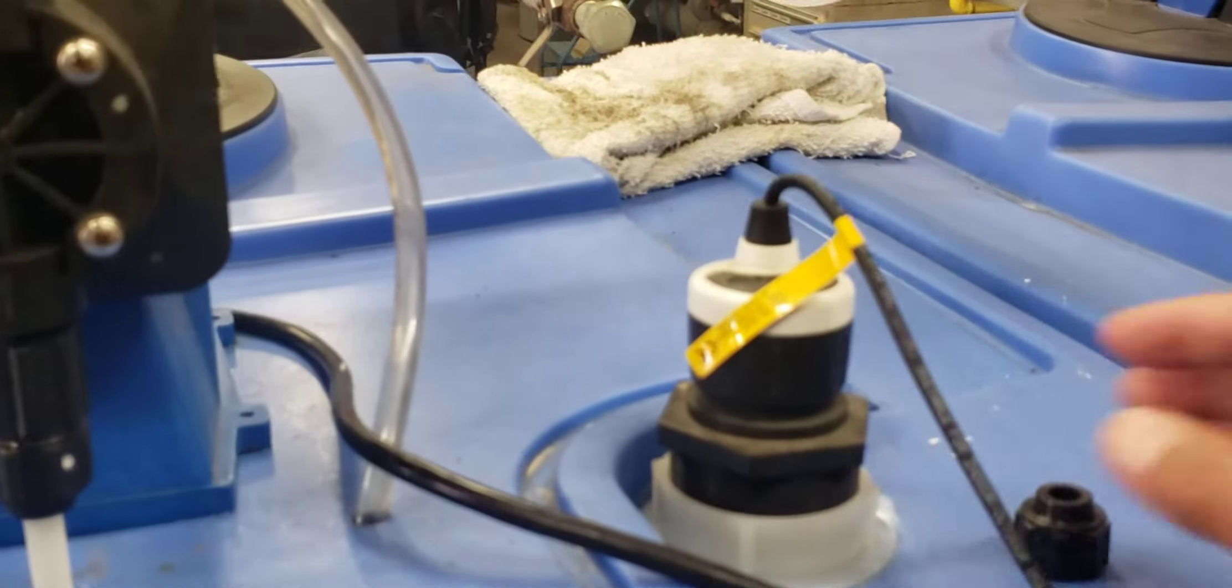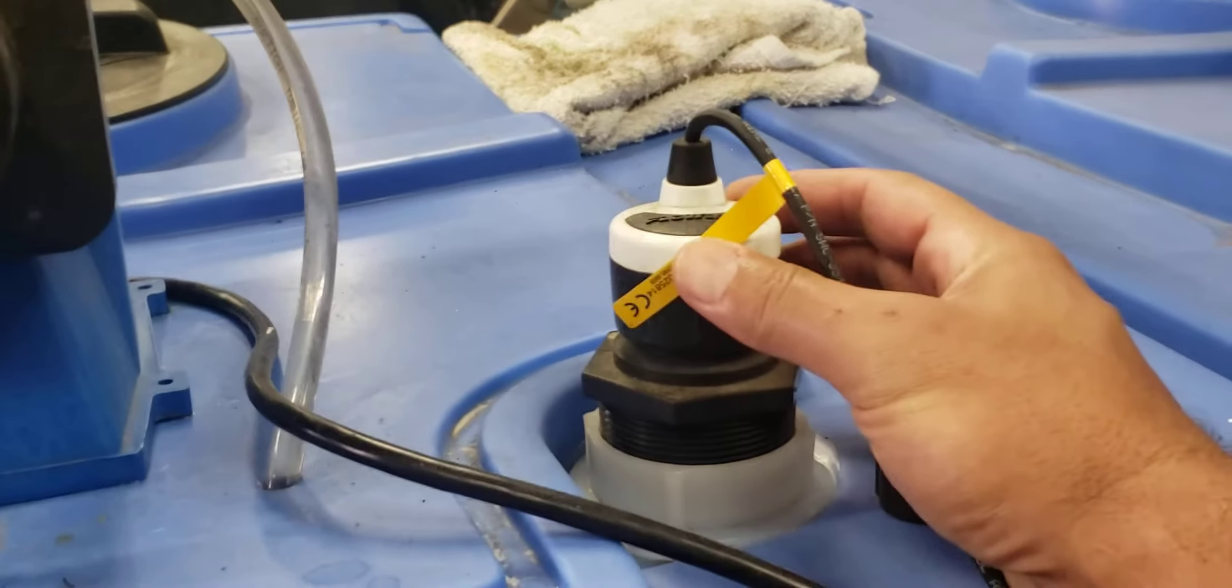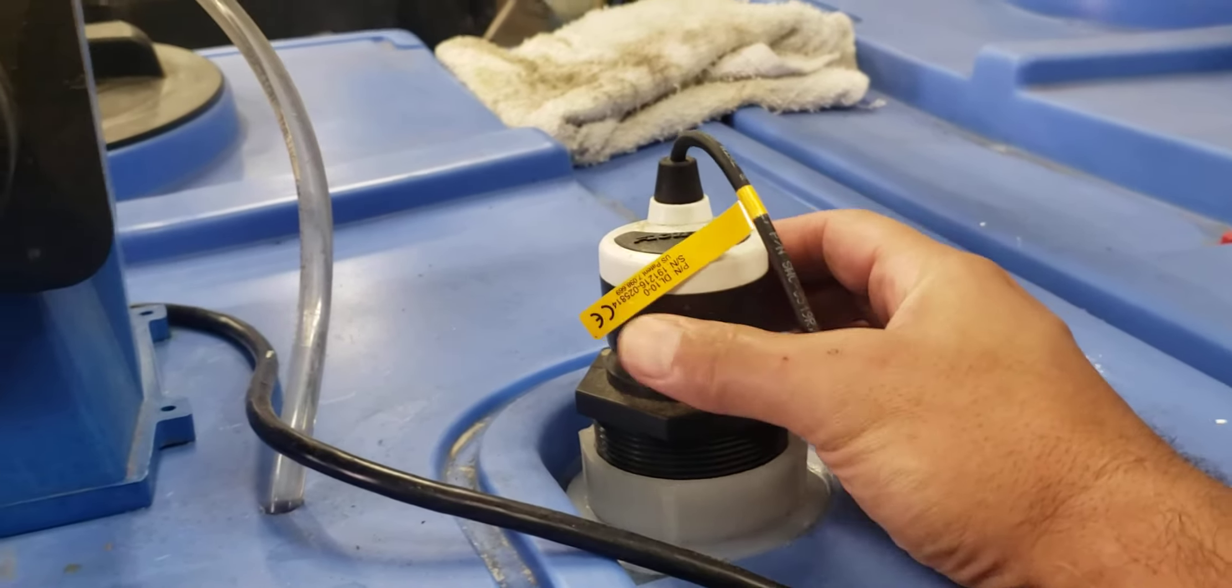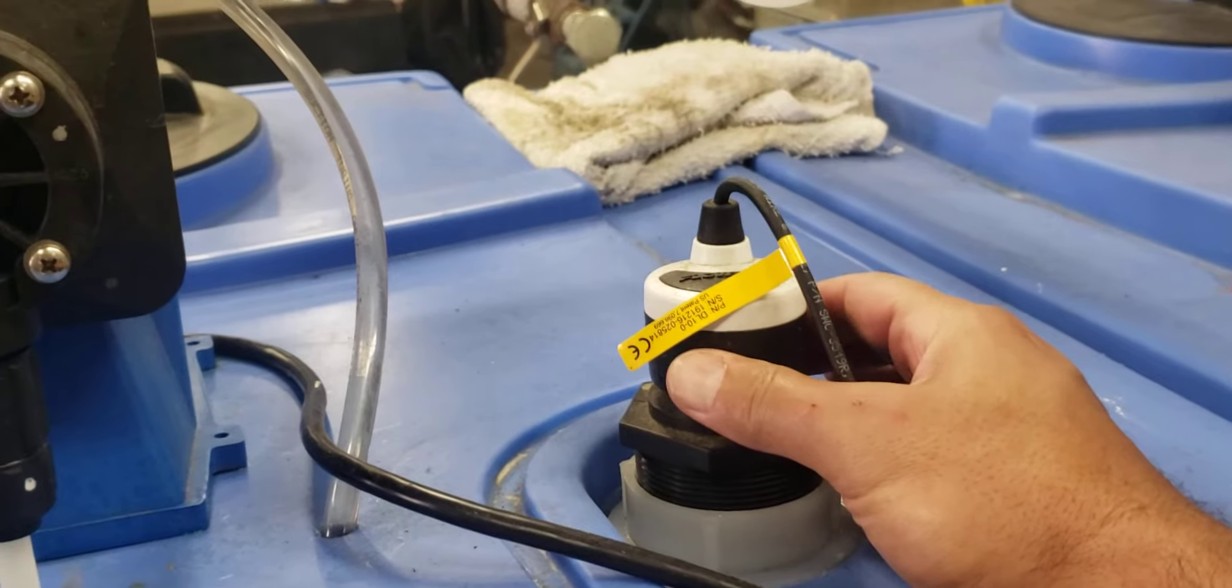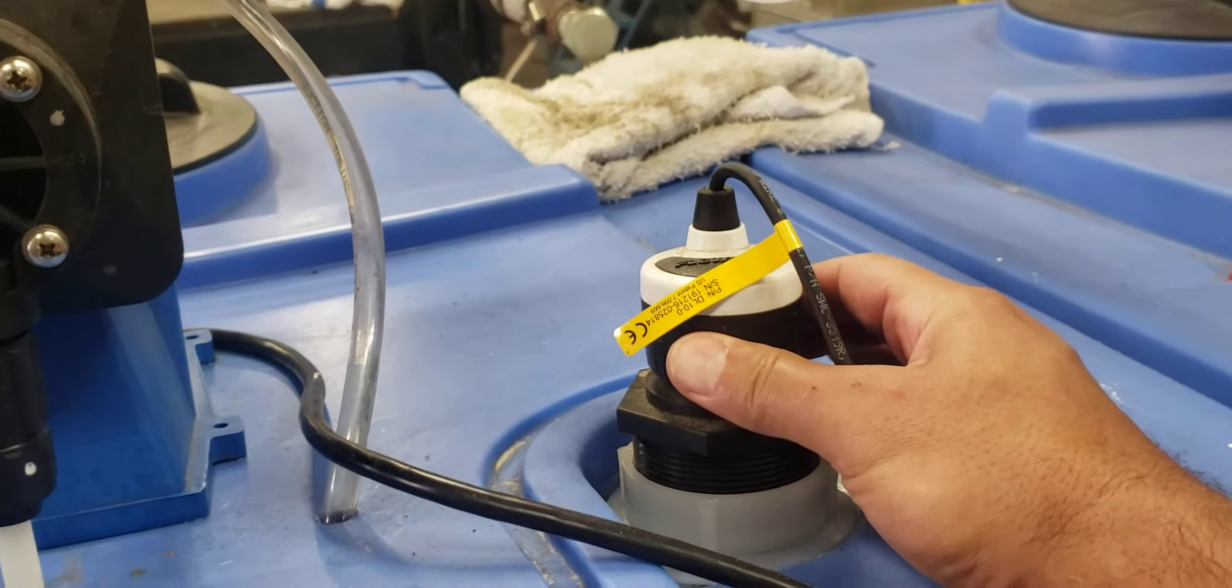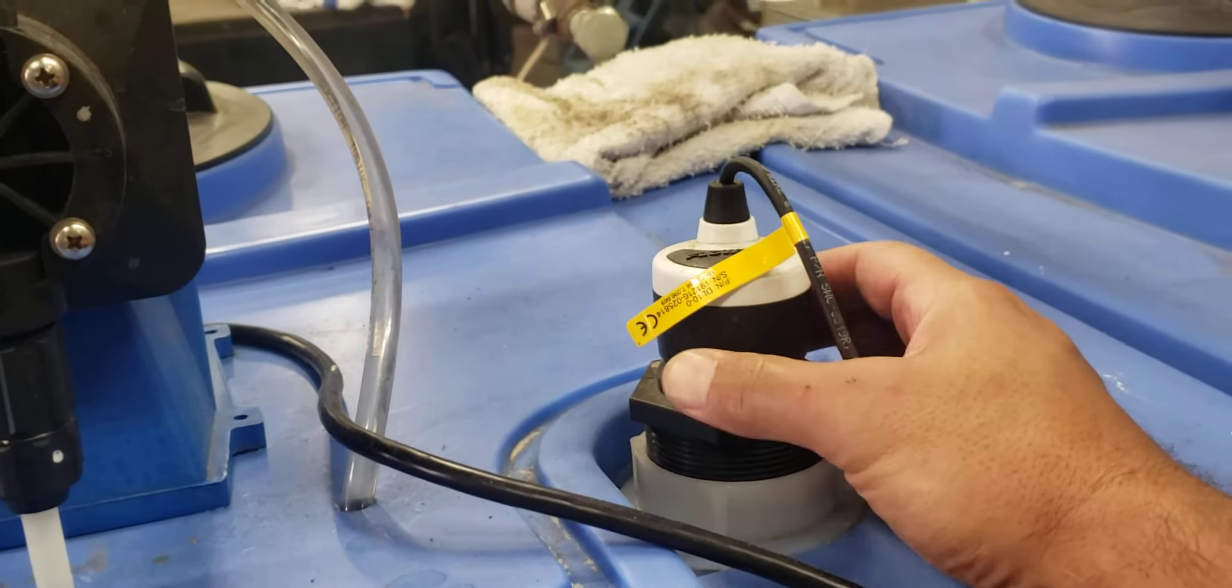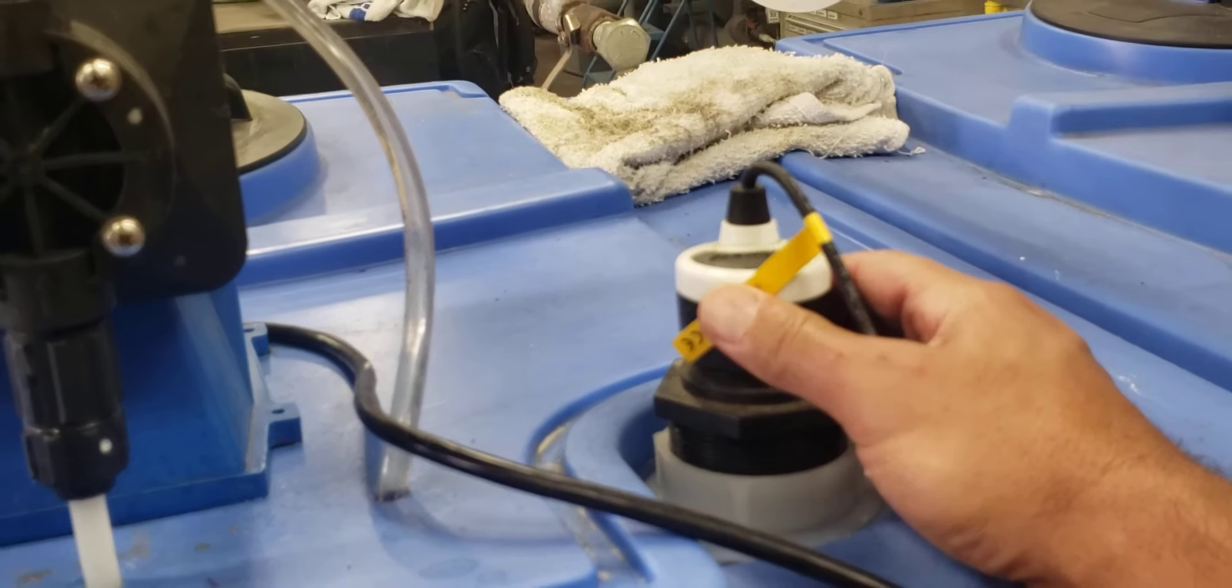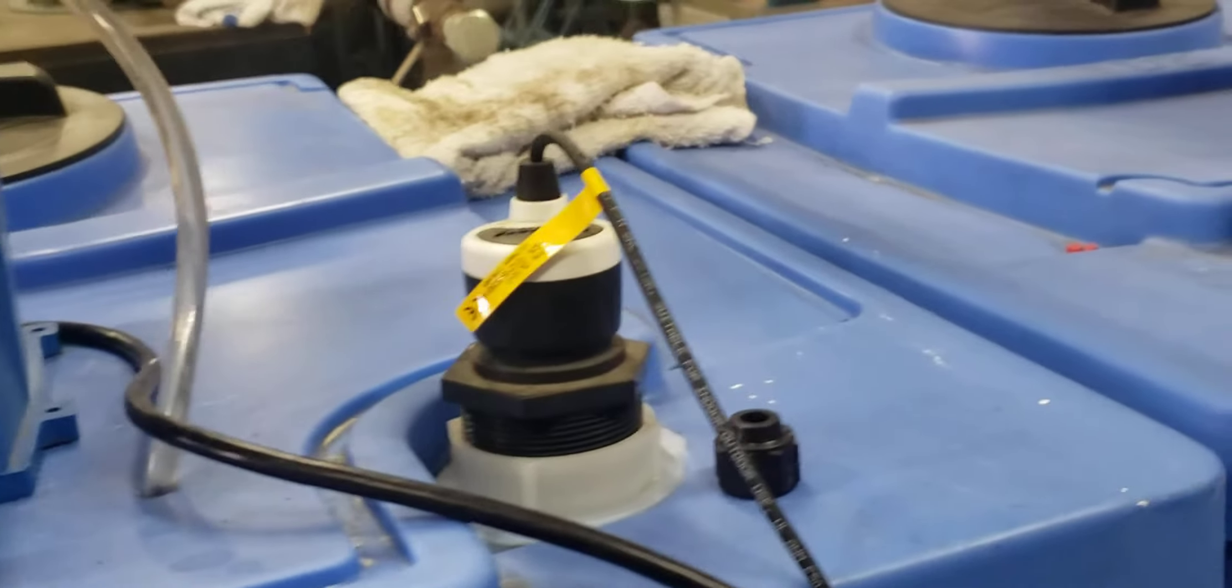And then like I said, this is the actual tank level monitor transducer right here. Correct. And this is the problem we had last time. When it goes empty and you fill it, sometimes it doesn't actually read that it went back to full again. And you have to power this down.